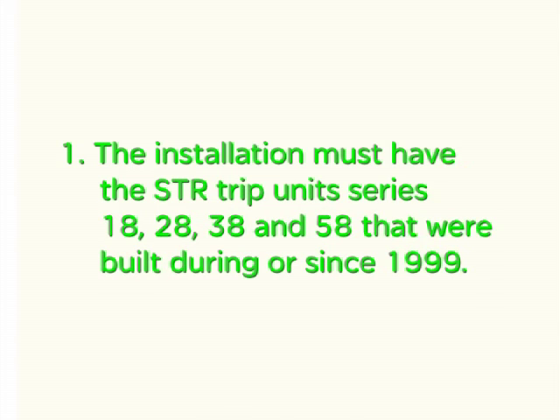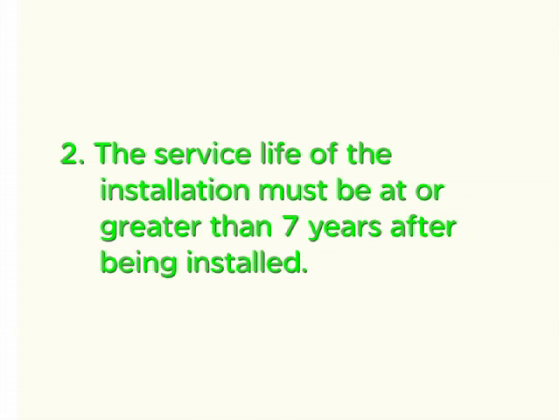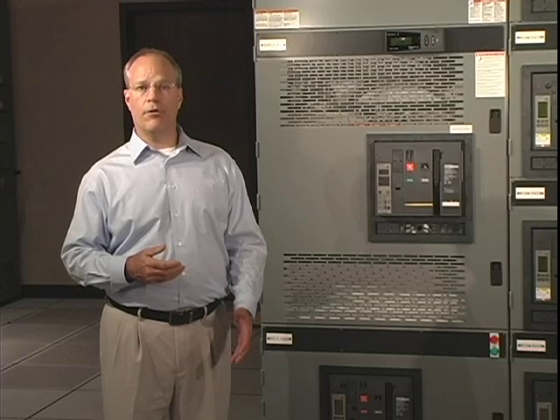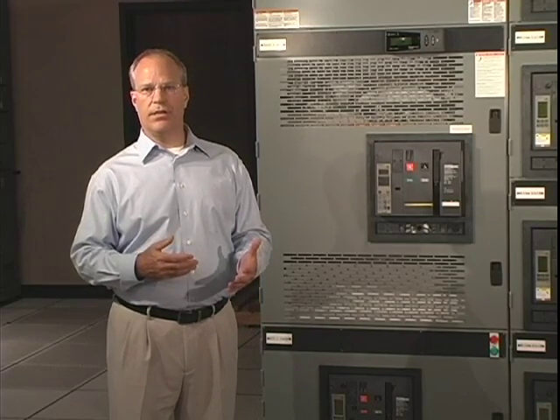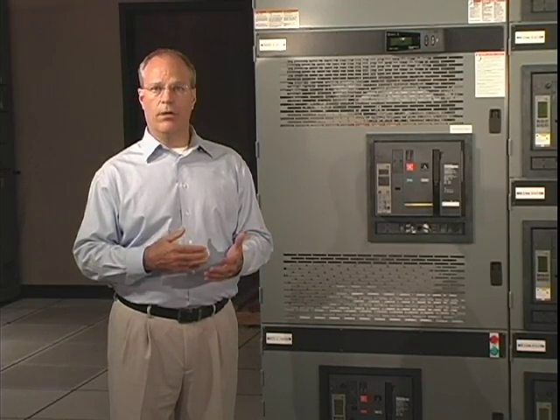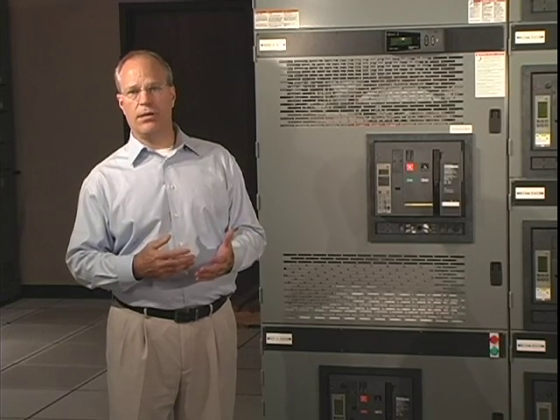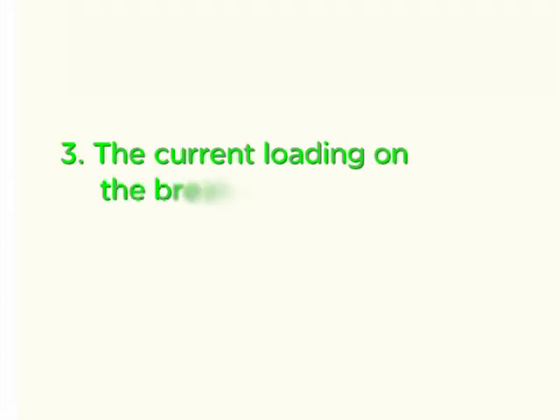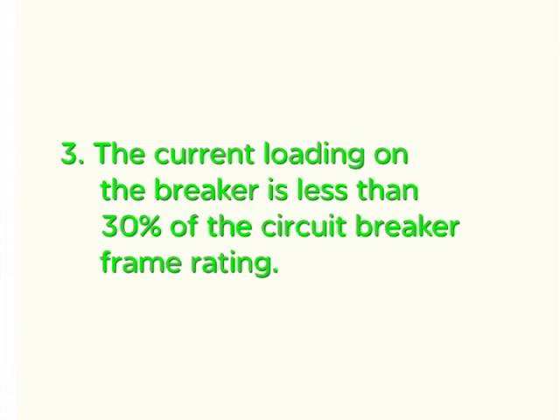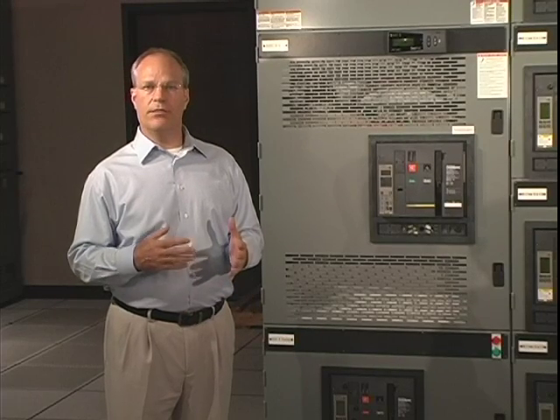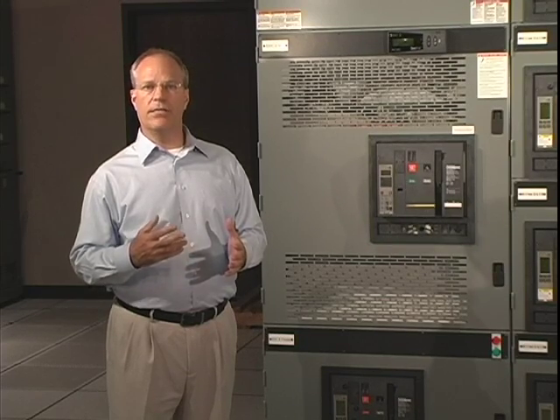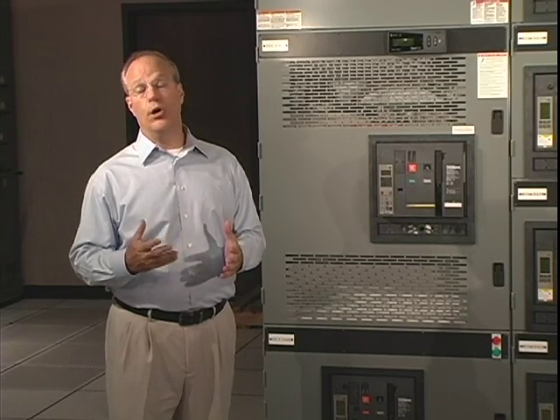First, the installation must have the STR trip units, series 18, 28, 38, and 58, that were built during or since 1999. Second, the service life of the installation must be at or greater than 7 years after being installed. And third, a low loading condition must exist, where most of these events have been reported to occur during the power up and power down cycle of the trip unit, where the current loading on the breaker is less than 30% of the circuit breaker frame rating. In the absence of these three conditions, Schneider Electric has not had any reported issues and therefore no action is required.